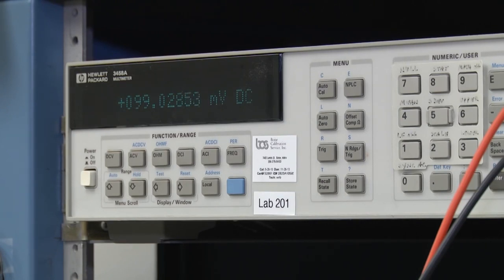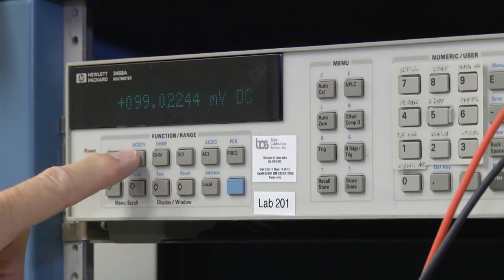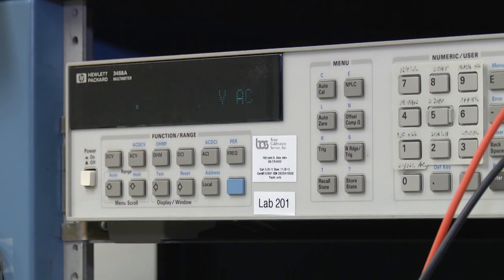Now the next thing that we're going to do is change the digital multimeter over to the AC volts function. And since the power supply is fully loaded at this point to its maximum rated output, we have an indication of less than 600 microvolts AC ripple, and that also is within specification for the HP power supply.